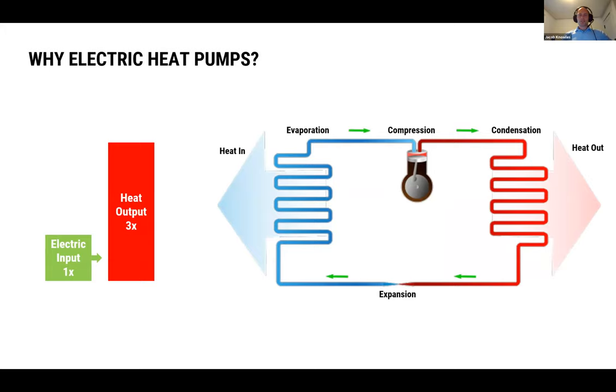You're not generating heat like a toaster, you're just moving the heat from either in the ground, like a ground source system, into the building in the wintertime, or an air source system, pulling heat out of the air. Yes, even freezing cold winter air, you can pull heat out of it and put it into your building. You can get one unit of energy in equals three units of useful heat put into your building. That's part of why it's so efficient and so low carbon.